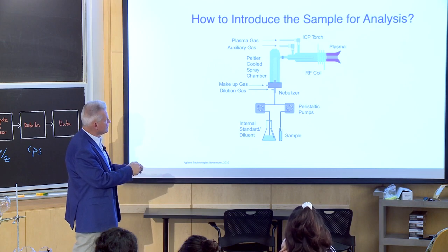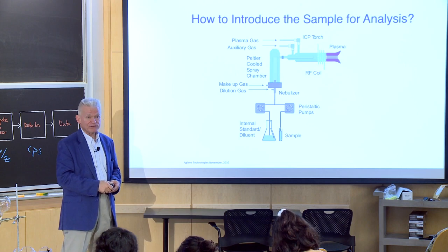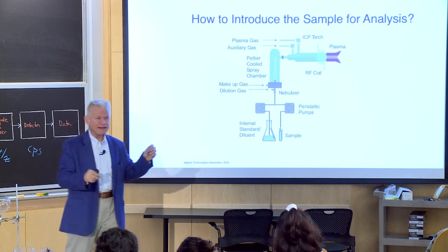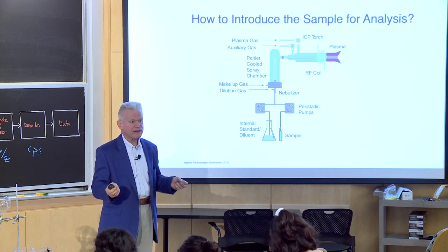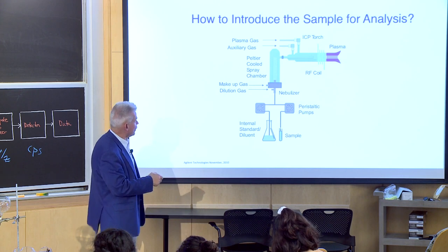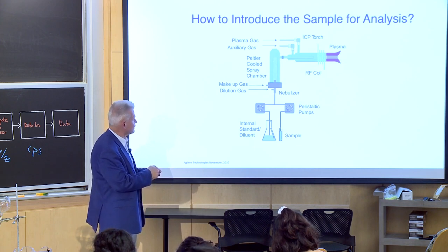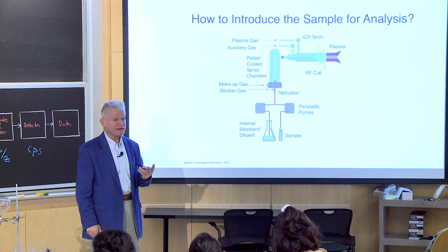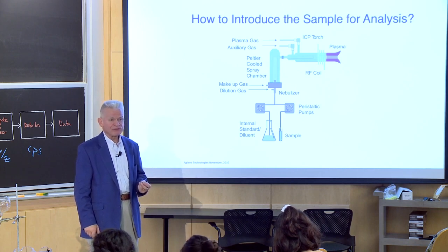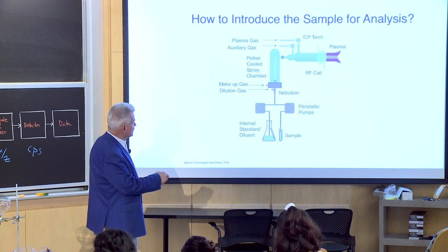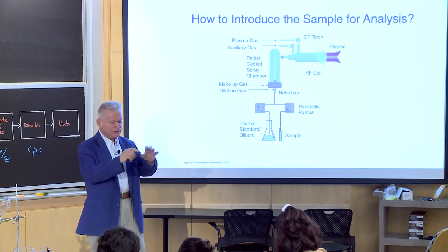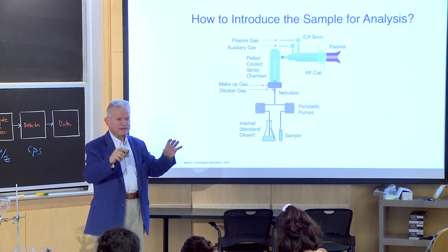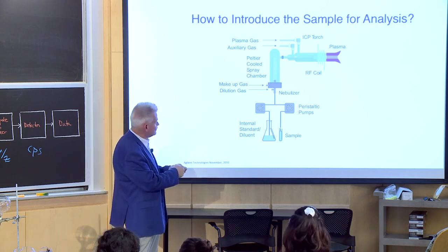Once they're down here, they have to make 2 right turns to end up outside the ion source. And those 2 right-hand turns cause the larger droplets to be pumped out and fall by the wayside. So the most sample that is actually going to enter this ion source is only about 2% of our original sample. We've gotten rid of the rest. Now, once it goes into this ion source, there are 3 concentric glass tubes. So the ions will go into the center tube here.